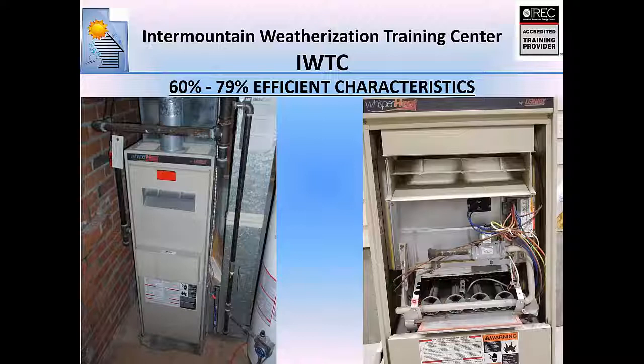Also note the burners. See the big louvered compartment here? That's so that when this is running, combustion air can get into these burners, so we get an air-fuel mixture. That's one of the visual characteristics of anything in the 60 to 79% efficiency range. And notice in this one, there is no inducer motor anywhere. That's another dead giveaway that it's less than 80% efficient: no inducer motor. We'll talk about this a little more.